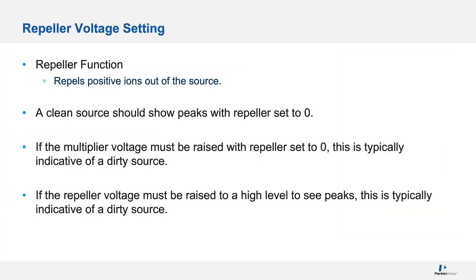The repeller function is there to repel the positive ions out of the source. So a clean source should show peaks with a repeller set to 0. If the multiplier voltage needs to be raised with the repeller at 0, this is typically indicative of a dirty source as well.